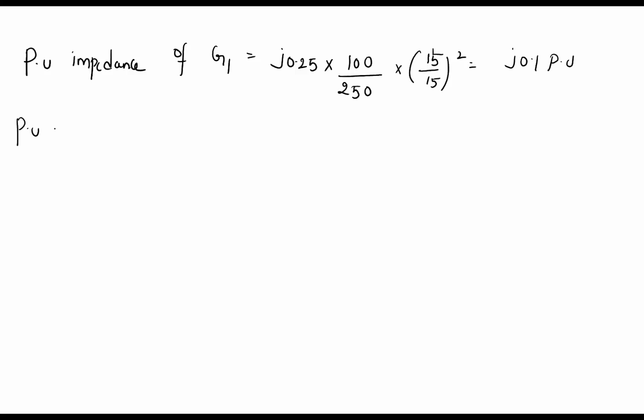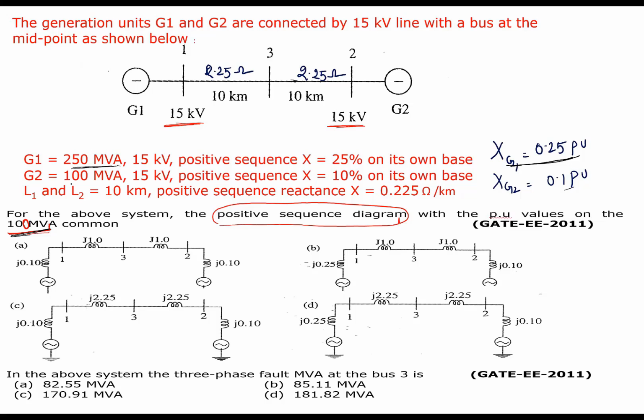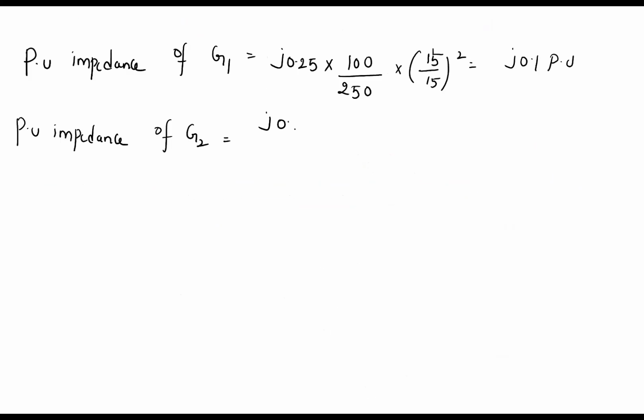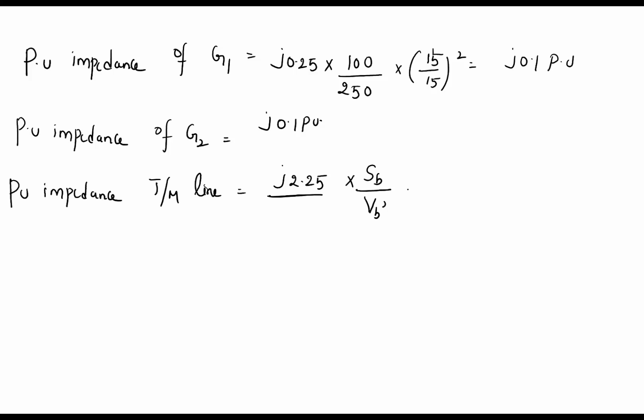Similarly, the per unit impedance of generator G2 will become j0.1. Here the machine MVA rating and our base MVA rating both match, so we need not calculate; it will remain the same, j0.1 per unit. Per unit impedance of the transmission line: here there are two sections, and both sections have actual impedance j2.25 ohm. Actual impedance divided by base impedance, where base impedance is S base divided by VB squared. So 2.25 multiplied by base MVA 100 divided by base voltage 15 squared. This value will become j1 per unit. The other transmission line value will also be the same, because both have the same impedance.